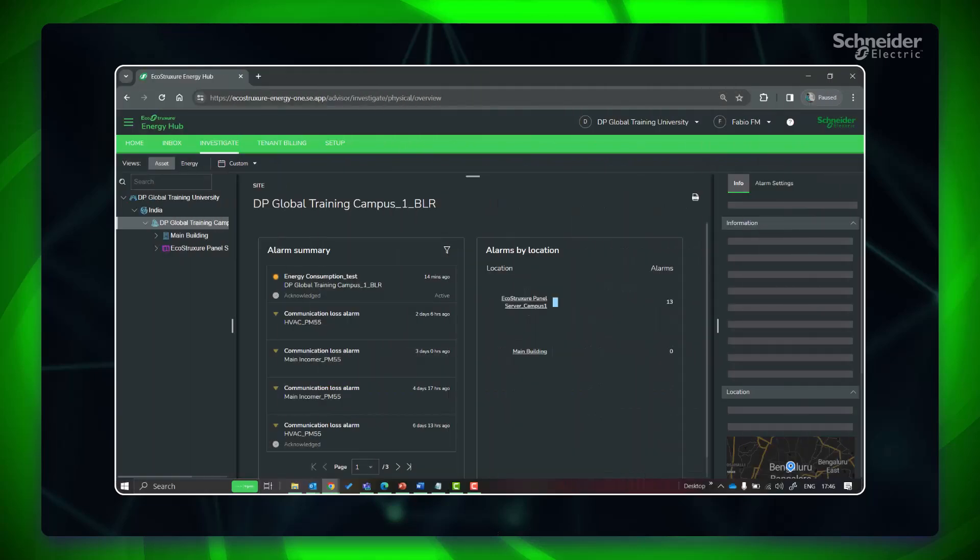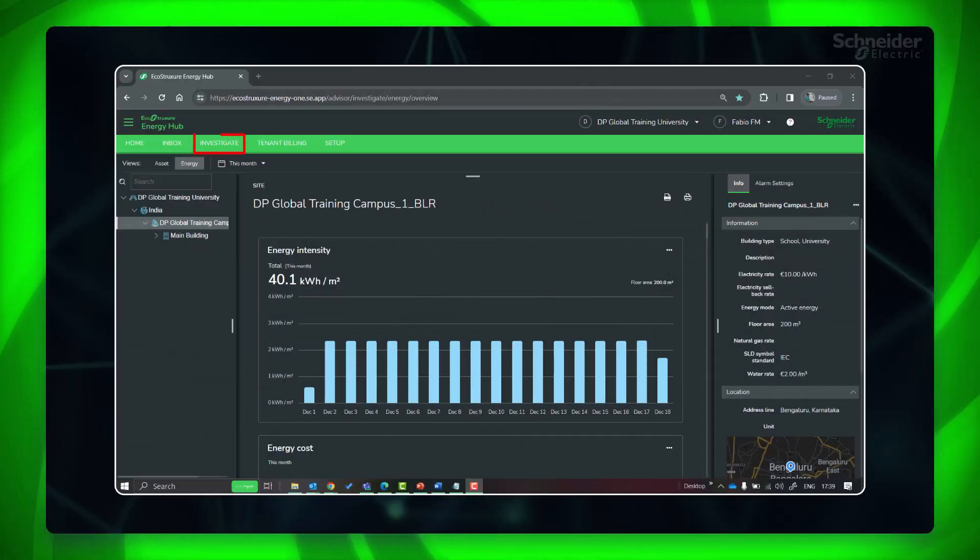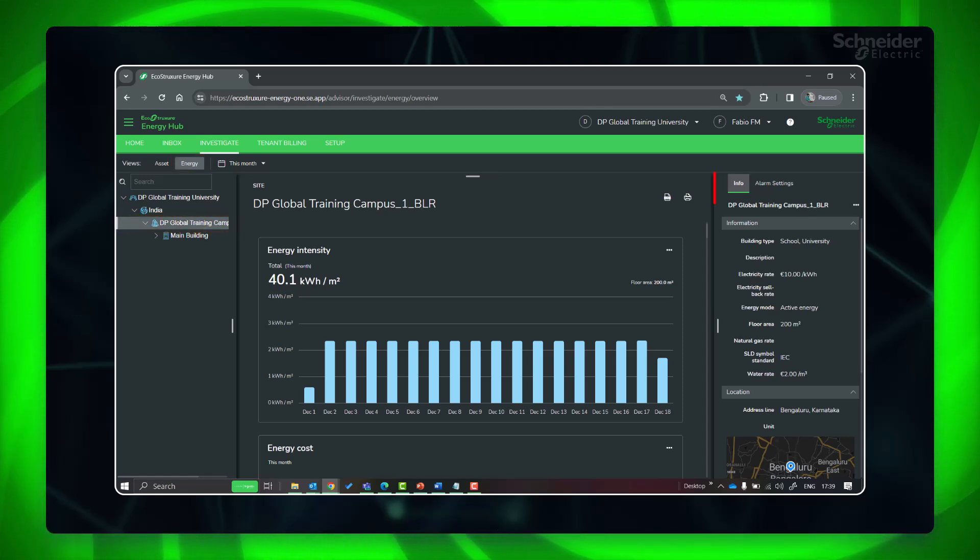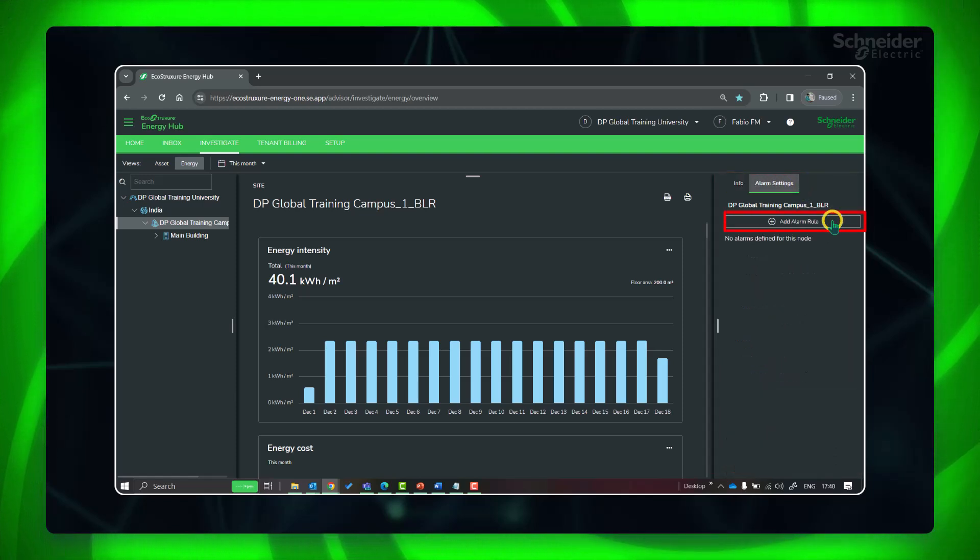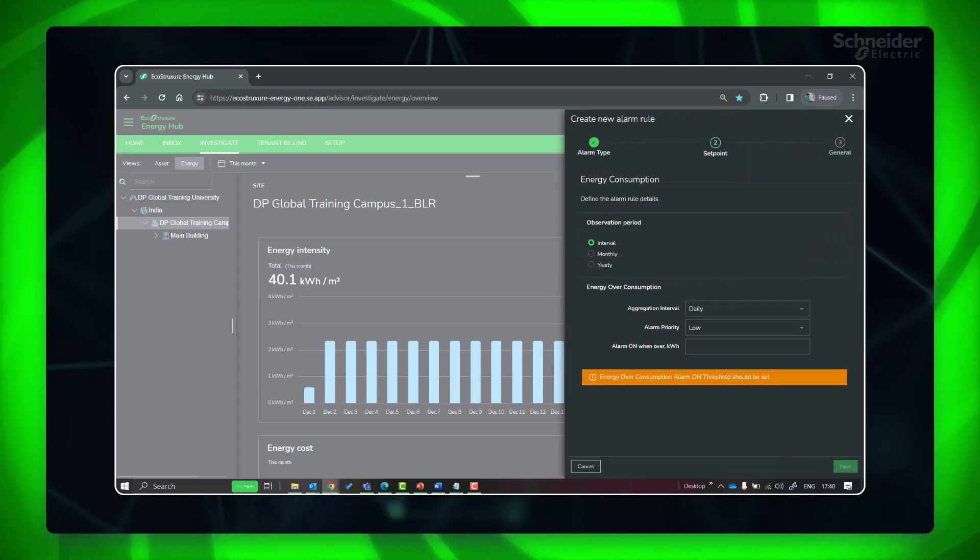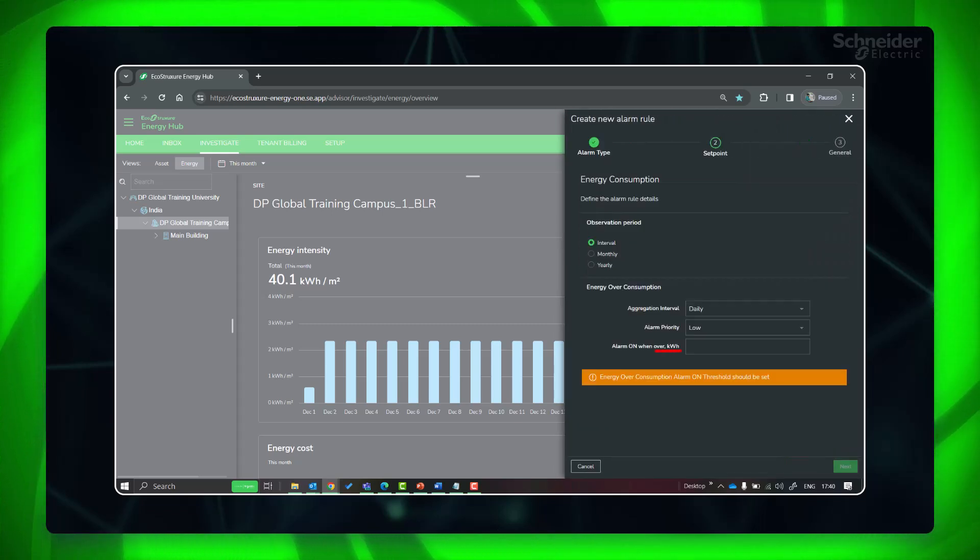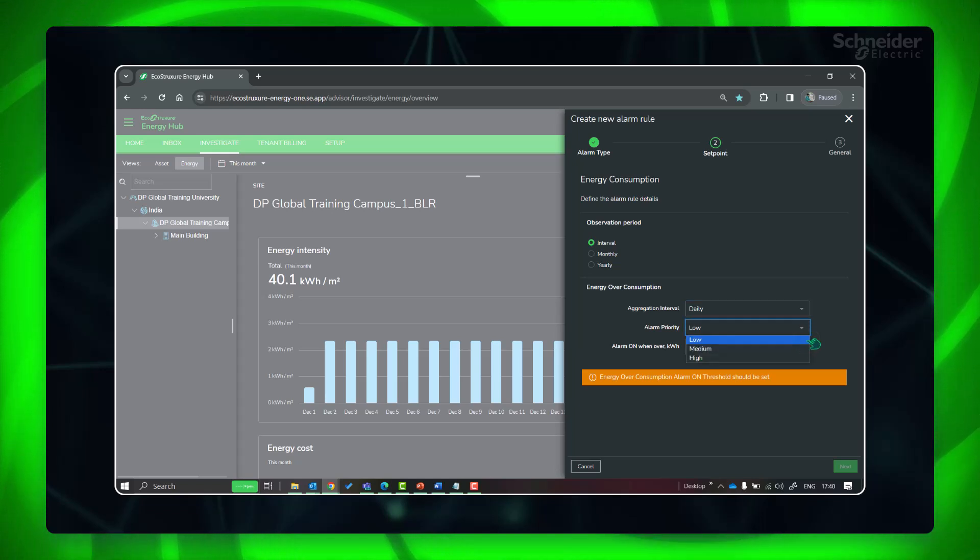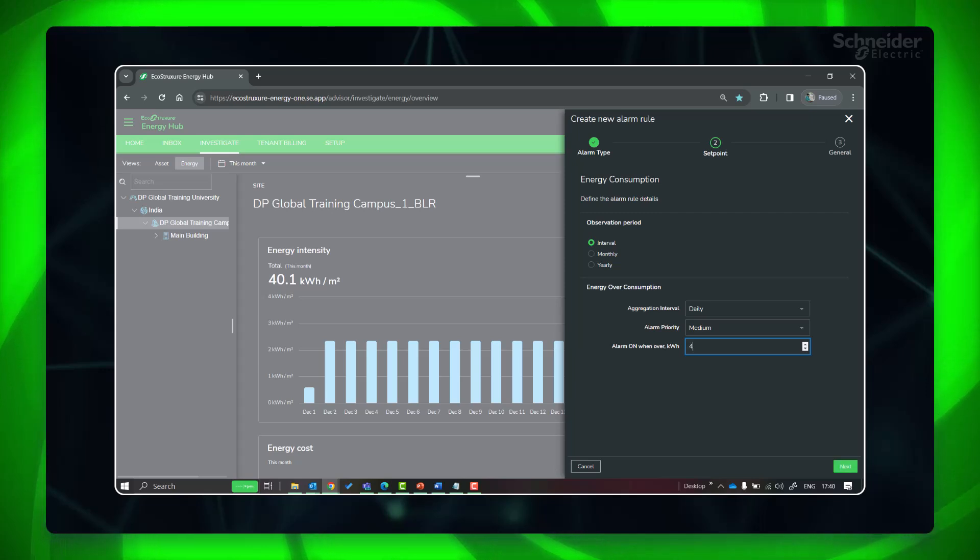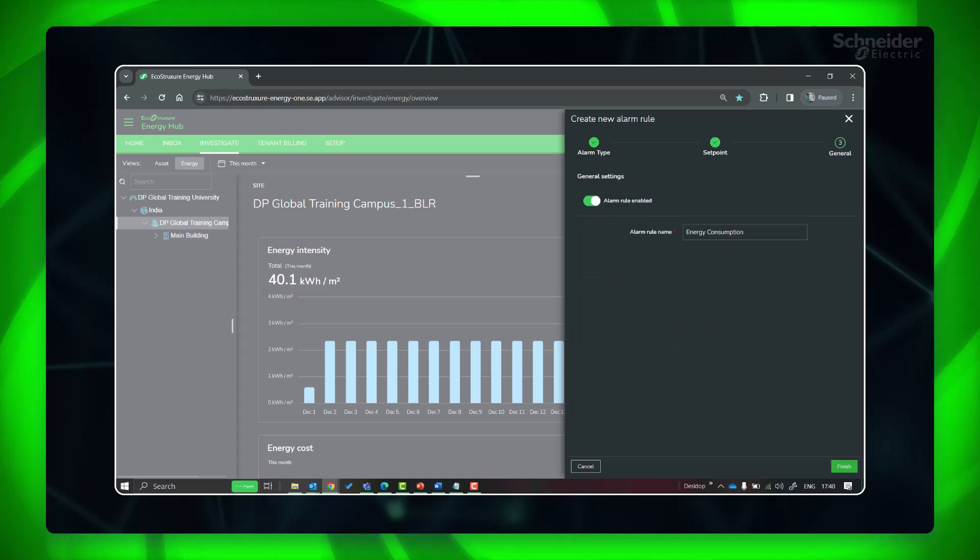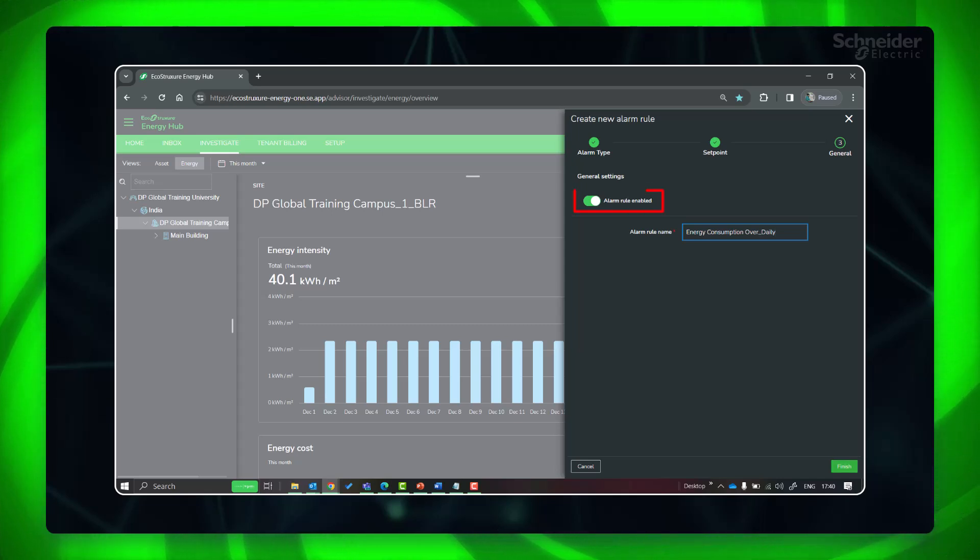For setting energy consumption alarm at site level, go to investigate and energy view. In the navigation panel, click on the site. In the information panel, click alarm settings, add alarm rule, select energy consumption, click next. Please note the alarm settings are as per active energy, irrespective of the energy mode you had selected earlier. Let's select interval daily, priority medium. Provide the daily threshold when we need this alarm to be on. Give the rule a name. Toggle the switch to on or off to enable or disable the alarm. Finish.